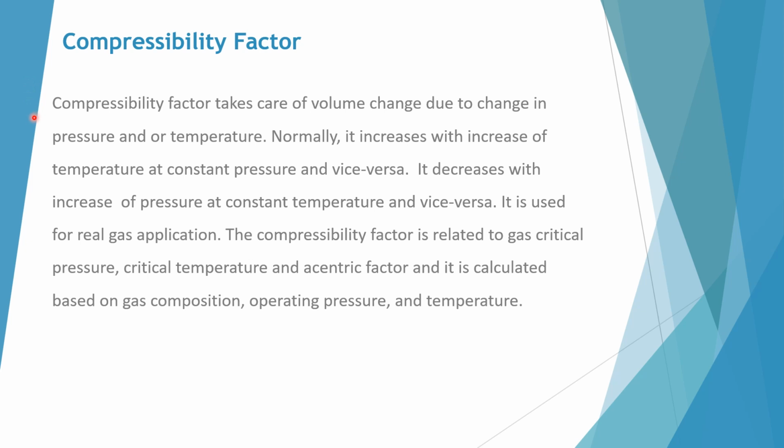Compressibility factor takes care of volume change due to change in the pressure and/or temperature. Normally it increases with increase of temperature at constant pressure and vice versa, and it decreases with increase of pressure at constant temperature and vice versa. It is used for real gas application. Compressibility factor is related to gas critical pressure, critical temperature, and acentric factor, and it is calculated based on gas composition, operating pressure, and operating temperature.